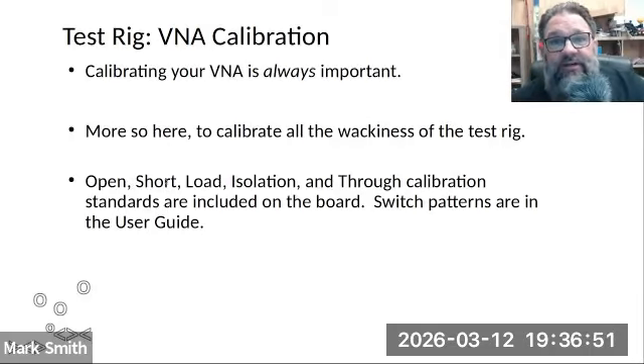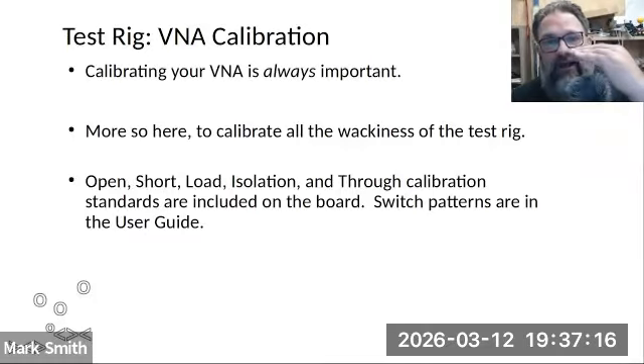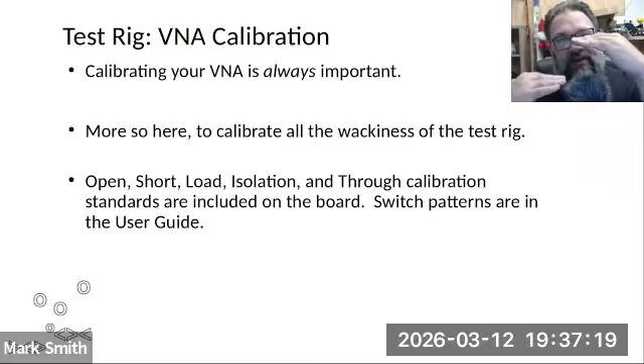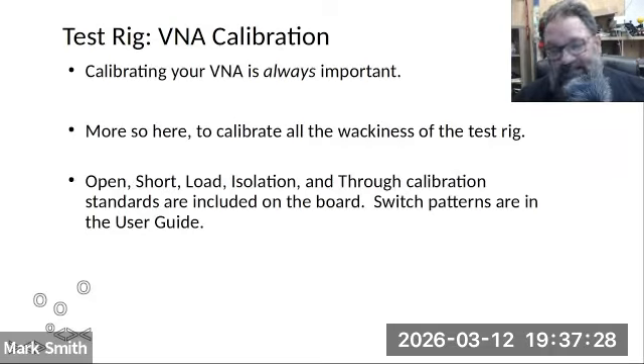Now, the good news is the kits that I sell have the open, short, load, isolation and through. They have all of the calibration standards on the board itself. So you don't need to use your little SMA caps. In fact, you can't on the current version. All of the calibration is done on the board itself. There are some switches on the back that you flip to put it in the right state to calibrate the correct way. And that puts the measurement plane right at that circuit board. Everything on the input side of that circuit board, on the VNA side, is calibrated out and does not show up in your measurements. Everything on the output side, by the device under test, is in your measurement. So it clearly defines where your measurement plane is.